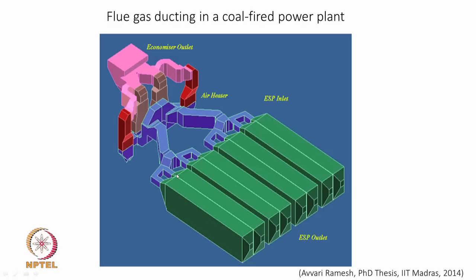The difficulty is that you have a duct that must feed a battery of four electrostatic precipitators, which are very large. The reason they are huge is that the inlet velocity can be on the order of 10 to 15 meters per second, but for best operation inside the ESP you need about 1 meter per second. To maintain the same flow rate, the cross-sectional area of the ESP must be very large — roughly 10 times larger — to achieve the reduced velocity of 1 meter per second.